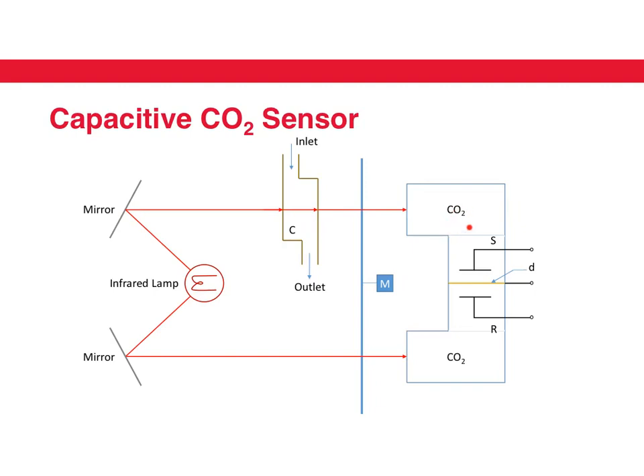This chamber receives less infrared light compared to the other, so the pressure here is lower. The diaphragm moves, the differential capacitor responds, and we can sense the change in capacitance.